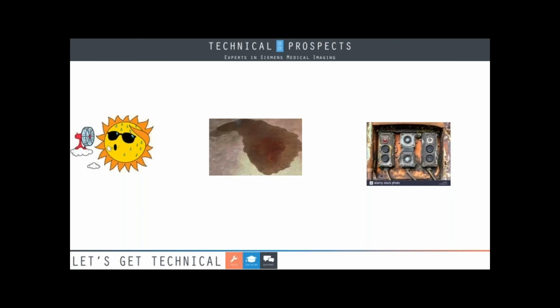Do you smell anything unusual? Or did the operator tell you they smelled smoke? Can you tell where it's coming from? Do you feel anything warm or hot? When you open a cabinet, do you see fluid dripping or anything? Is there dust everywhere? Dust caused from patient gowns can be a huge problem in power cabinets. Power cabinets and components should be vacuumed at least every preventive maintenance.